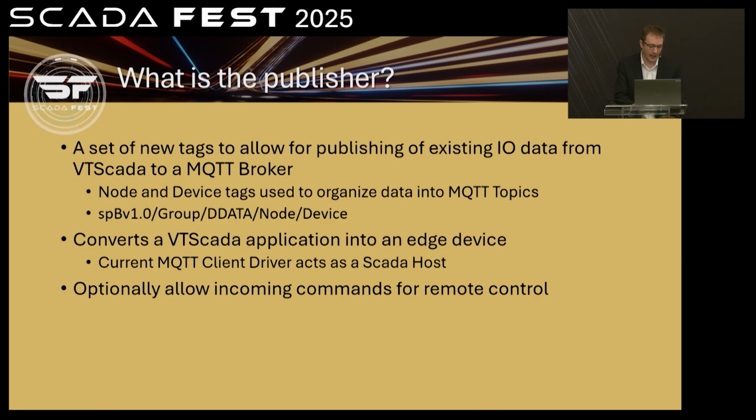And I'm working off a development branch, so you'll see some new things going on, but we are going to allow incoming commands to come into your SCADA system as well. It's optional. It defaults to off for security reasons. You probably don't want people remotely sending commands to your PLCs mostly, but there may be some users that actually want that functionality, so it's something you can configure if you wish, but it defaults to not having it.